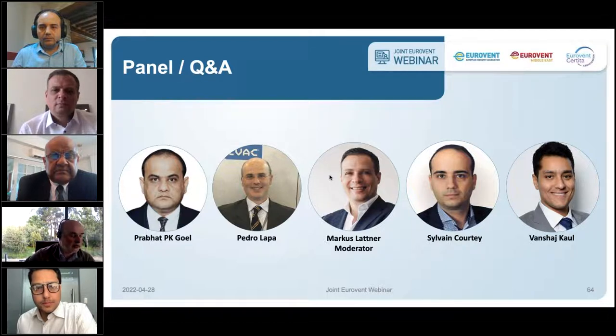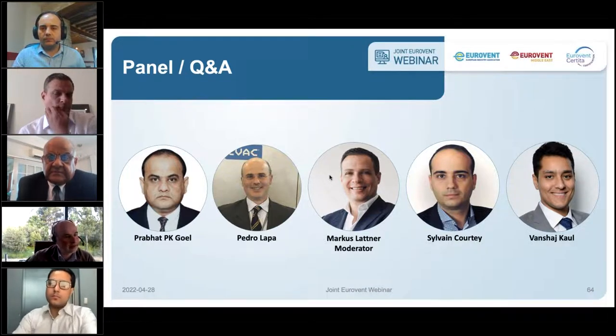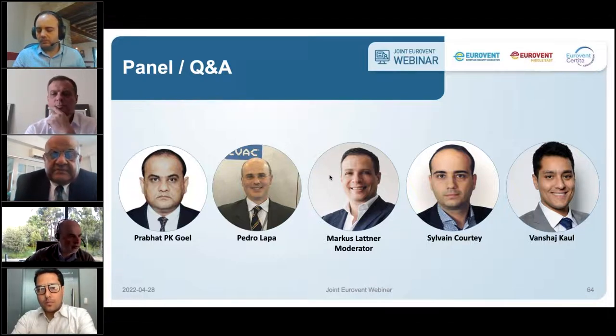But there are other places that are not so humid, but we need to find a way to reduce the energy consumption in the units. That way could be indirect adiabatic cooling, which would be very useful in dry places. When the climate is dry, we need to increase the delta T between the inside and outside, so doing indirect adiabatic cooling, we promote that. Another solution is the bypass mode in the heat recovery component, because, as an example, here in Portugal we have one of the hottest climates in Europe, but not so hot. We have big mid-seasons, so between summer and winter is a big period. In that climate, the bypass is very useful, because what we need is reducing the pressure drop in the units to save energy.